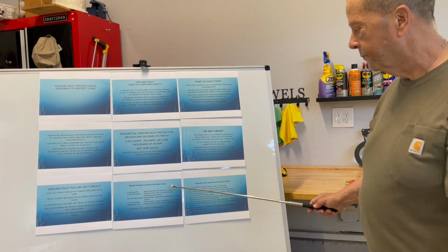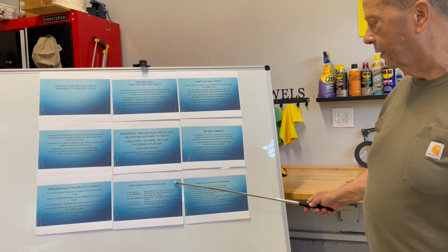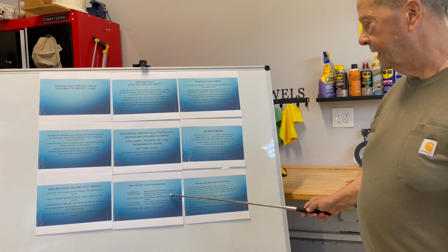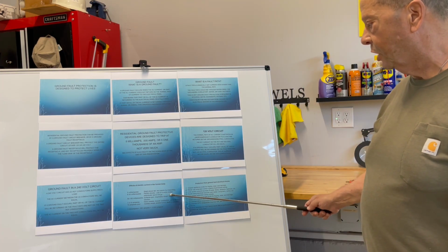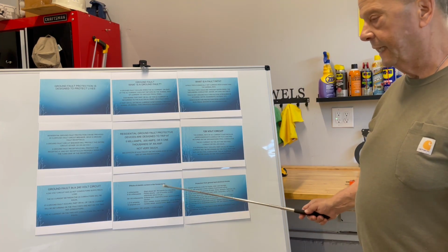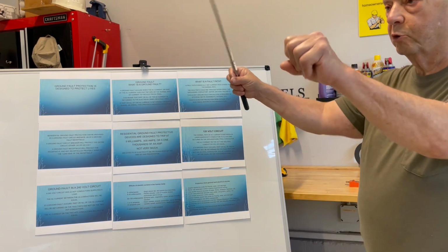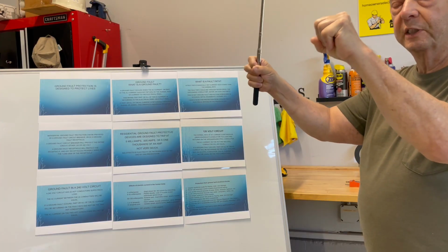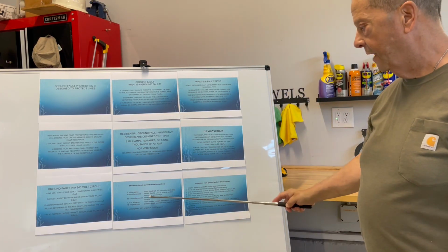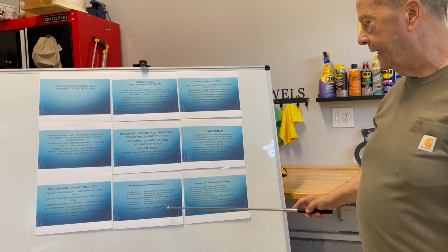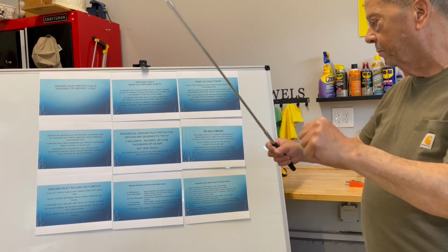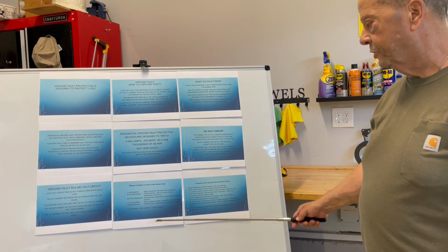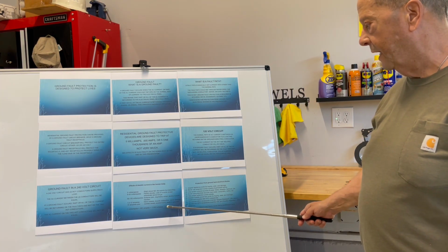Effects of electric current in the human body. 5 milliamps, you will feel it. At 6 milliamps, painful shocks, loss of muscle control. You can't let go. There's many stories of electricians when they're working, they get caught and they can't let go because their muscles contract. At 50 milliamps, extreme pain, could have respiratory arrest, severe muscle reactions. At 1 amp, your heart could cease, nerve damage. 10 amps plus, cardiac arrest. You're really in a lot of trouble there, okay?